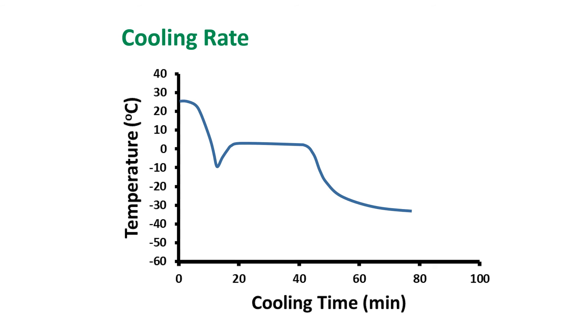The measurement of the freezing point depends on the cooling rate. The cooling rate can be calculated from the slope of the initial temperature versus time curve, in degrees C per minute. A faster cooling rate decreases the supercooling temperature and thus decreases the measured freezing point. Therefore, the cooling rate should be optimized — the optimal cooling rate is one below which there is no significant change in freezing point. However, a very slow cooling rate could be less sensitive to determining the freezing point.